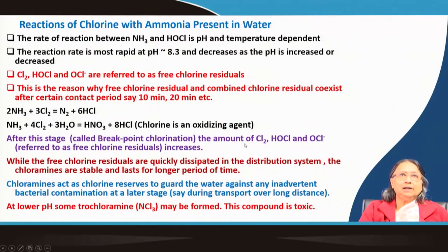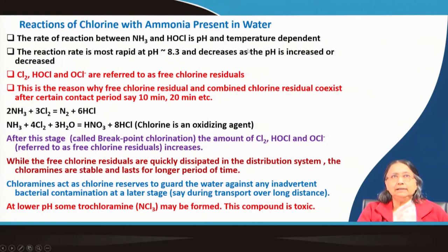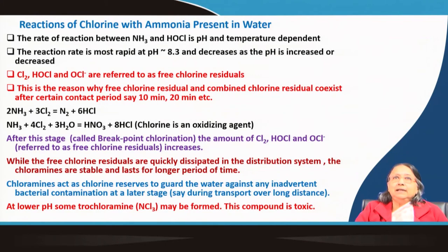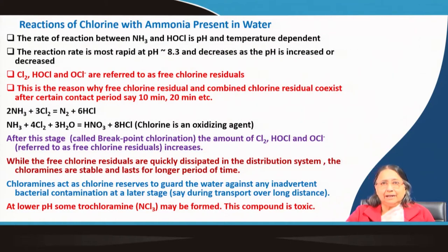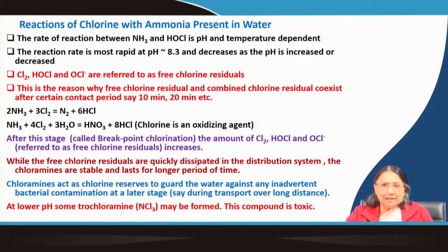The rate of reaction between ammonia and HOCl is pH and temperature dependent. The reaction rate is most rapid at pH 8.3 and decreases as the pH is increased or decreased. Cl₂, HOCl, and OCl⁻ are called free chlorine residuals. Free chlorine residual and combined chlorine residual coexist after a certain contact period — say 10 or 20 minutes. If ammonia is present, some chloramines form and some free chlorine remains — it is basically a mixture.